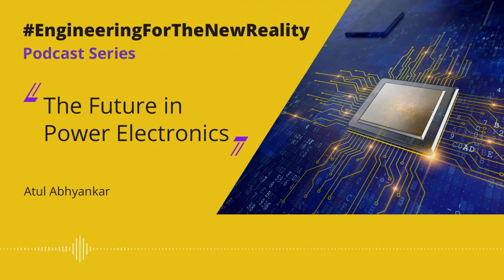To achieve all this, replacing the chargers is not going to be an easy job. So the drive will be on making the chargers digitally controlled, where the charging algorithms for various different kinds of batteries can be flashed onto the controller. We need to make provision for this when we design the power electronic circuits with their controls, so that any new technology in batteries which comes in, the power electronics should be able to cater to it.